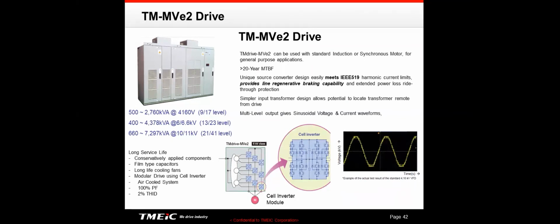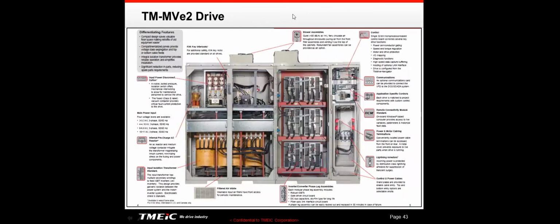It also is regenerative. Most drives, whether they be low voltage or medium voltage drives, are not regenerative. If you try to slow a drive down too fast, or you've got something where water pressure is pushing the drive, or you've got a downhill conveyor or something, that drive is simply going to trip. This particular drive, because it has an active front end, is also regenerative. And this particular drive can also supply VARs to you if you want to use the excess capacity in that drive to correct your power factor in your building. That's a picture of the MVE2 drive. It's got an isolation transformer, and then your converter and your inverter are in the cells.